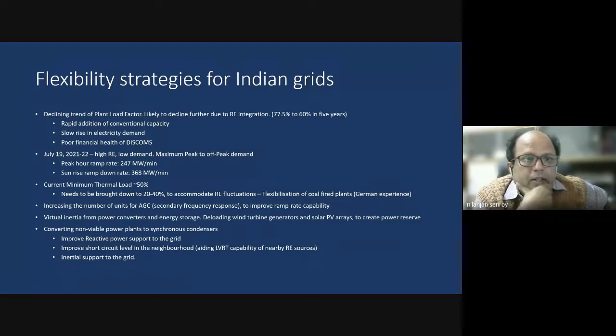So it was found that a peak hour ramp rate of 247 megawatts per minute was expected, and similarly the sunrise ramp down rate was about 368 megawatts per minute. So at sunrise the solar switches on, and when the solar switches on, the thermal generation, which would have been online already, has to be backed down. So the ramp down rate during sunrise is 368 megawatts per minute. And this is a huge number, tremendous number.